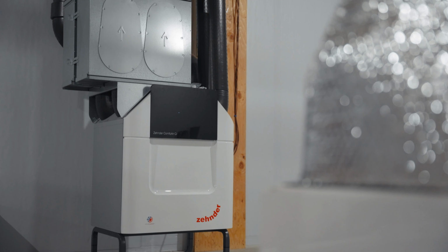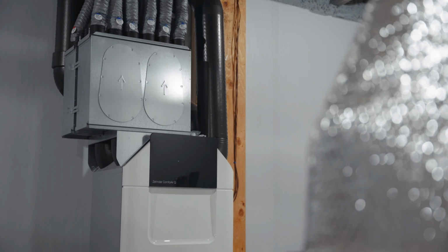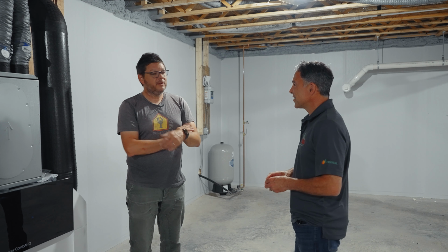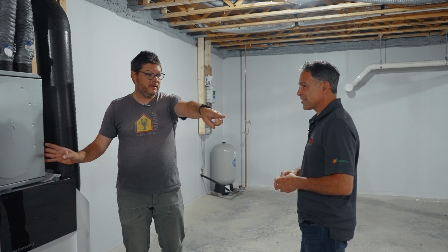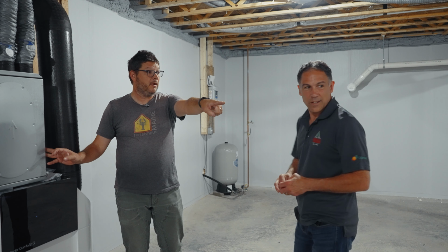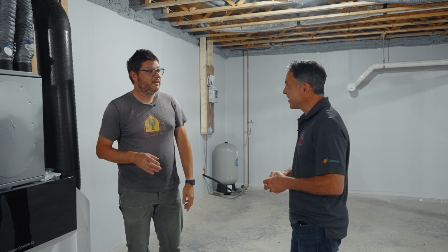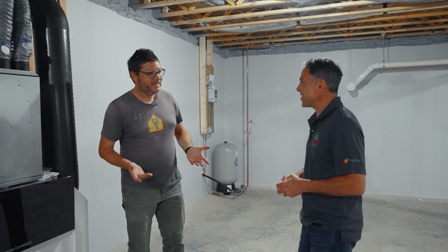A lot of people install ERVs today, and a lot of HVAC contractors are starting to put them in. The building code outside of Rhode Island requires it—Rhode Island's eliminated that for some reason. But what they do is take the ERV and tag it into the ductwork that's already there, thinking, oh, we already have ductwork, let's put it in there. That doesn't work.